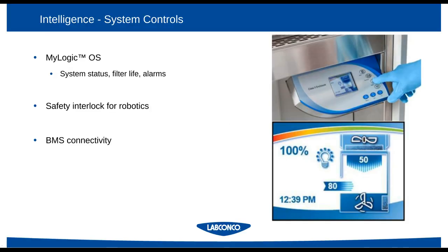Controlling the system is also really important as well. The interface on a biosafety cabinet is really the hub for users to understand what's happening with an enclosure, whether the filter life is needing to be replaced, understanding alerts and alarms, and doing so with screens and images that help quickly resolve issues rather than just simple beeping noises and difficult to understand alerts. So that's done on our platform using the MyLogic operating system.